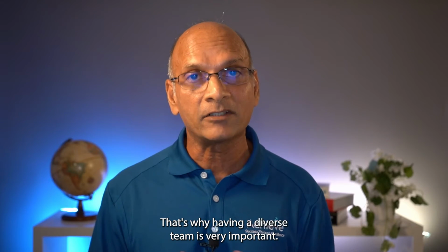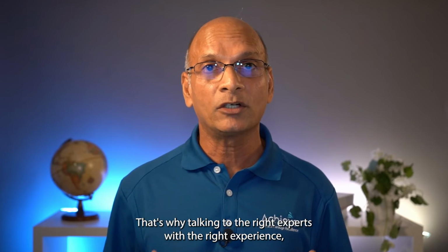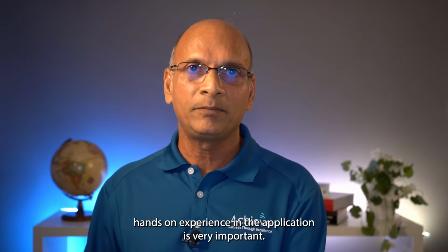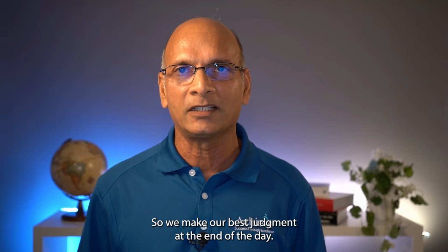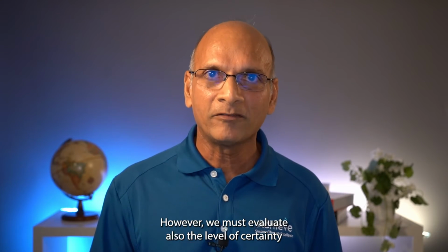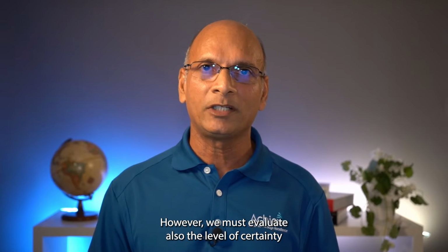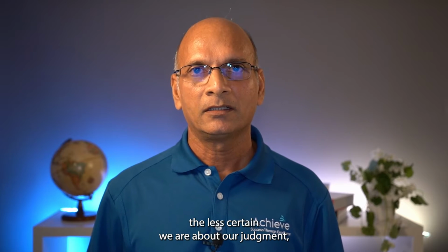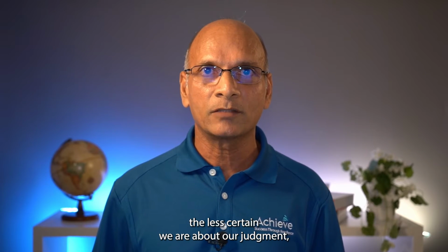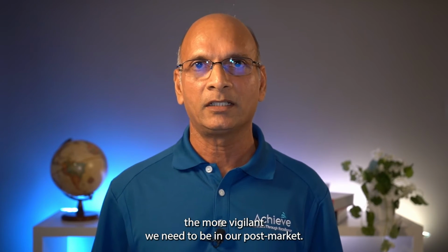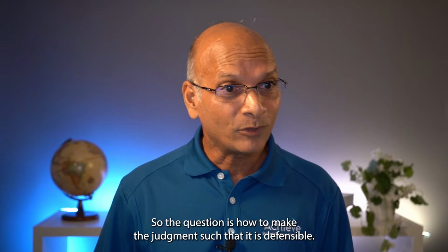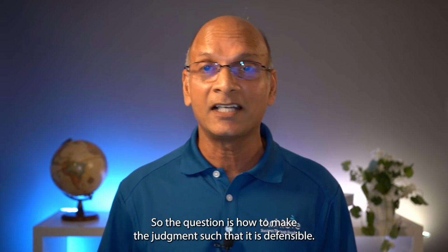That's why having a diverse team is very important. That's why talking to the right experts with the right experience, hands-on experience in the application is very important. So we make our best judgment at the end of the day. However, we must evaluate also the level of certainty we have in that judgment. The less certain we are about our judgment, the more vigilant we need to be in our post-market. Bijan, you are asking a question. So the question is how to make the judgment such that it is defensible.